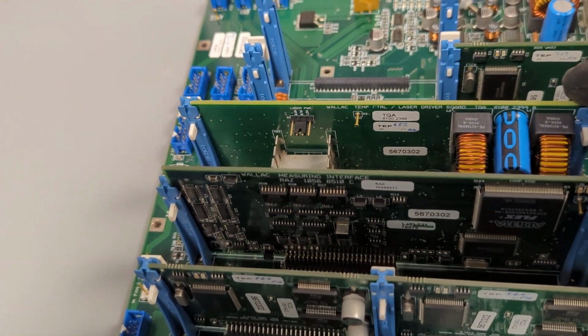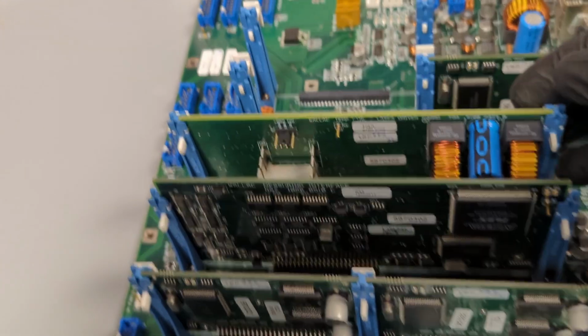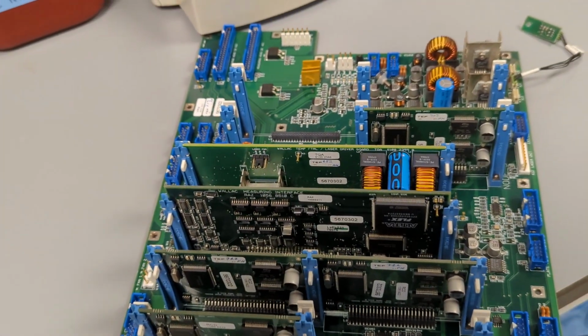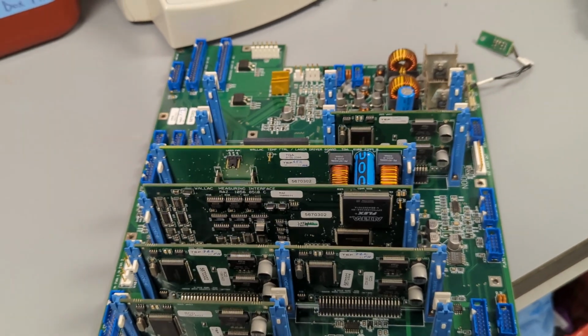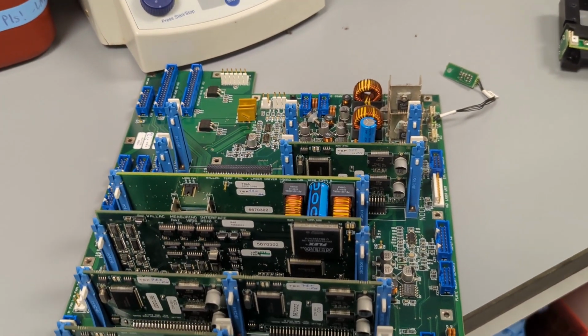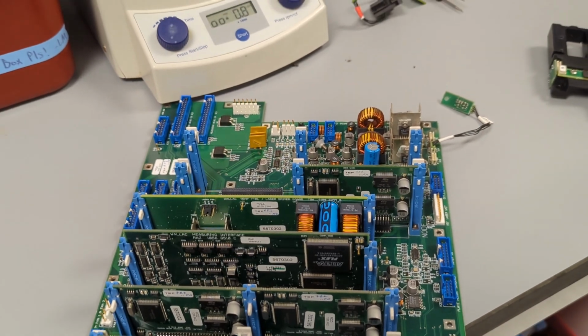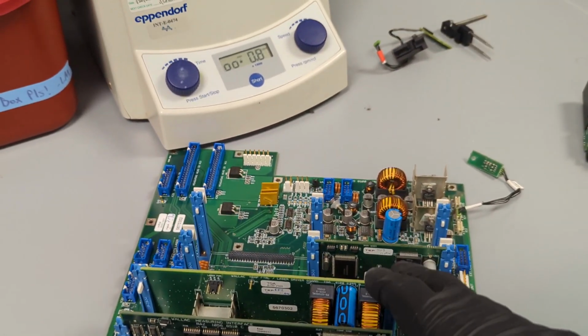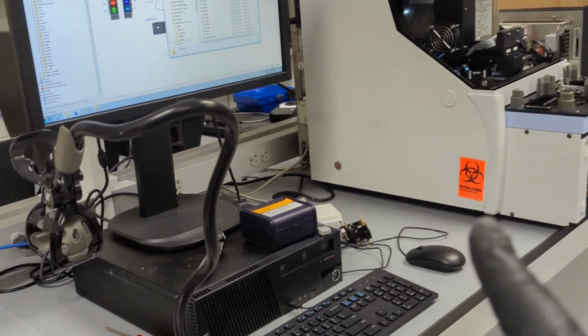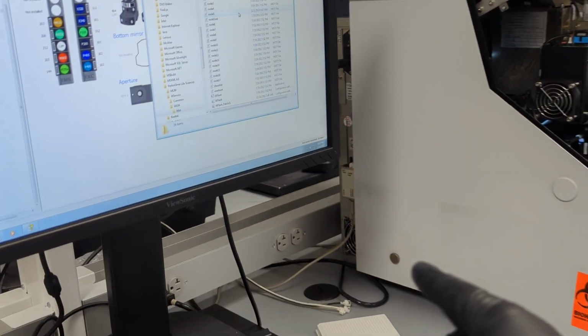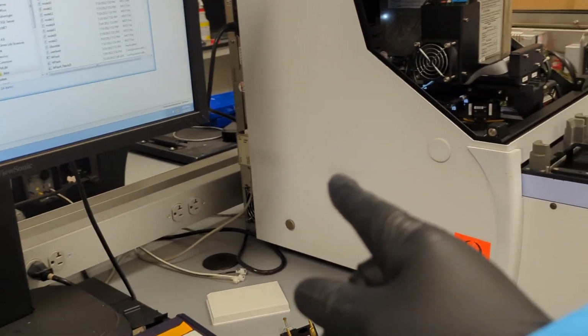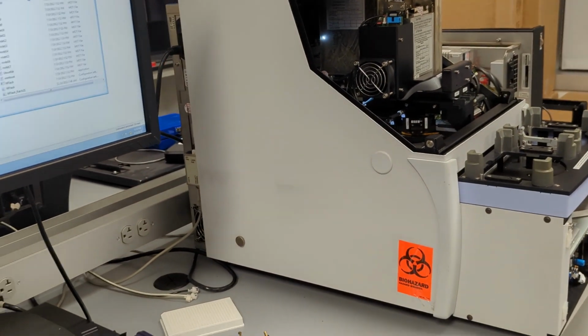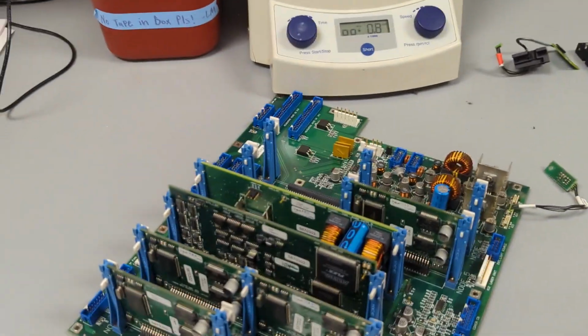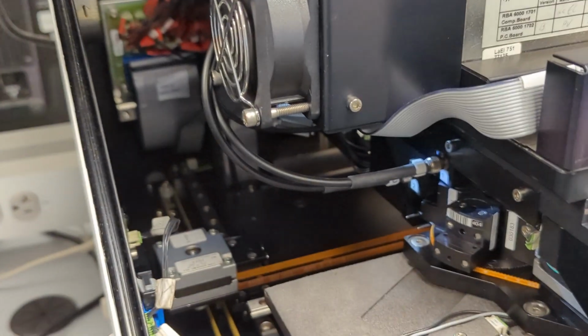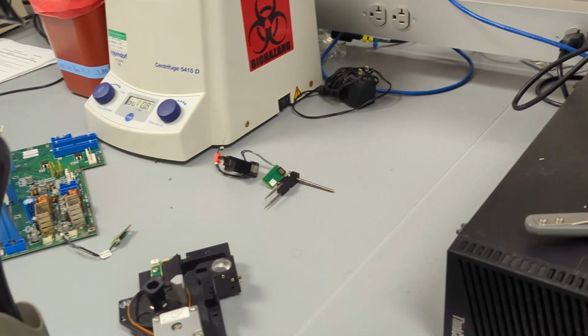This looks like your temperature control and laser driver board. Depending on what option you've got, these units also have an additional excitation light source that is a laser for what's known as AlphaScreen assays, which I'm not going to get into, but I believe this 2104 is outfitted with that, and that laser is also hanging out in the back of the instrument, and then there is an optic cable that brings it to the measuring head.